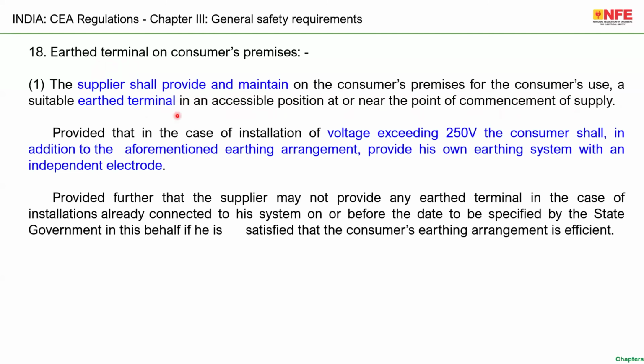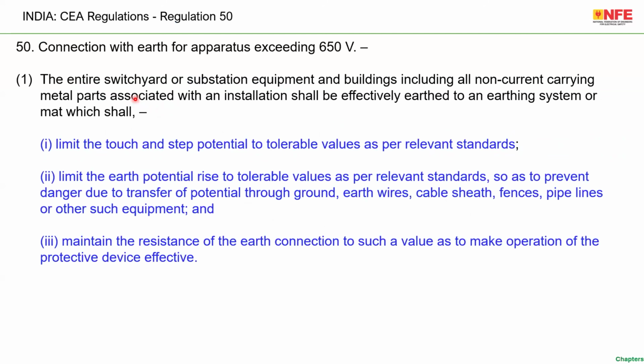Now, further explanation on this earthed terminal or continuity conductor you can find in regulation number 74, which says up to 33 kV along the overhead line, there has to be an earth continuity conductor as well, with one side of the earth continuity conductor connected to the neutral of the transformer, the other side connected to the earthed terminal. I have a picture, I will show you.